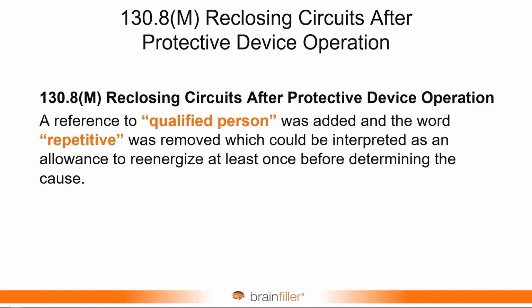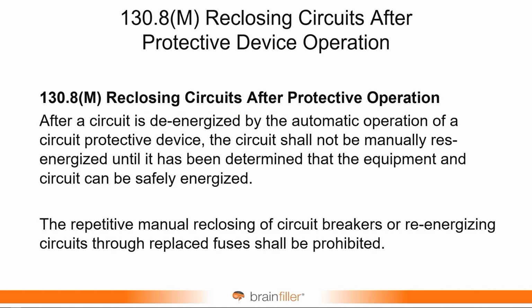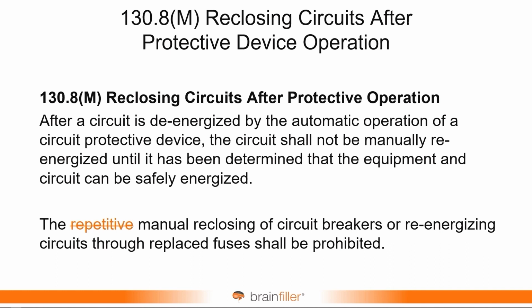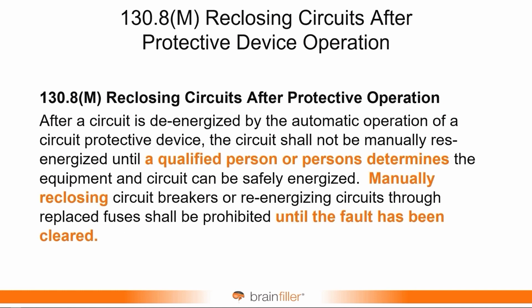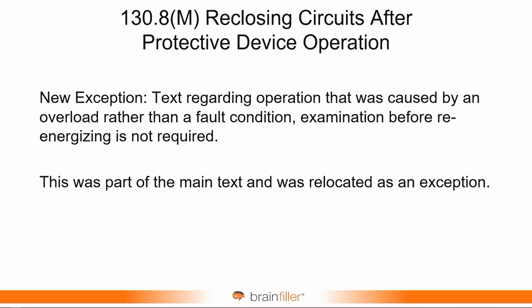There is now a reference to a qualified person, and repetitive was removed. Let me explain why. This is the language that we did have. There was no reference to a qualified person, and down at the bottom it says repetitive manual reclosing is prohibited. The reason repetitive was removed is it implies, well, I'm not going to do this repetitively, I'll just do it once. And the thought was, no, you shouldn't do it at all until a qualified person has determined why this has tripped. So the language now: as a qualified person determines the equipment and circuit can be safely re-energized. Manually reclosing until it's been determined why the device tripped is prohibited. Now, there was some text that referred to an overload. If it was caused by an overload, then you don't have to examine before re-energizing.